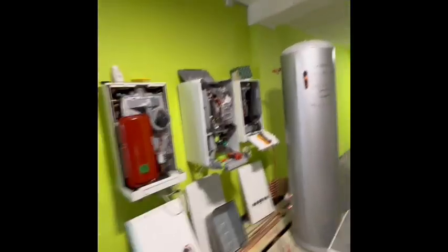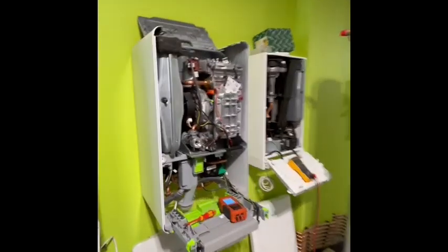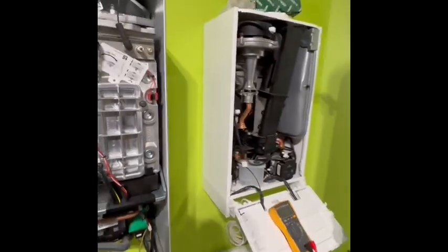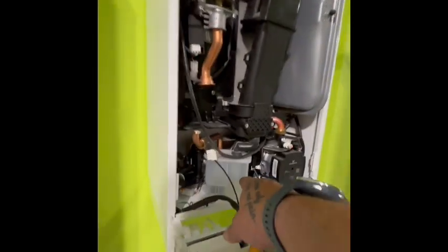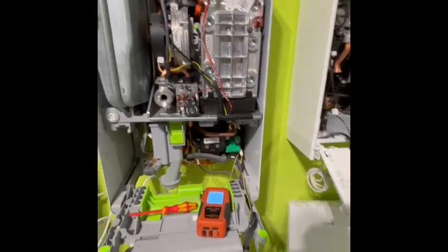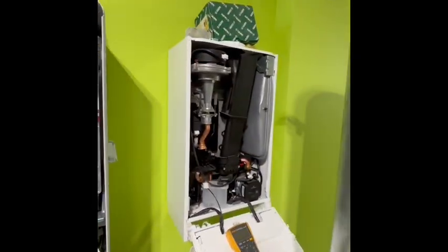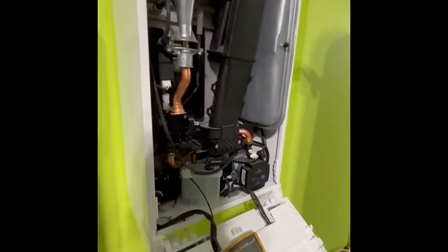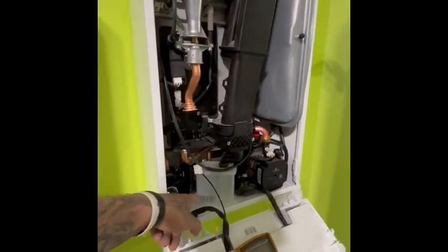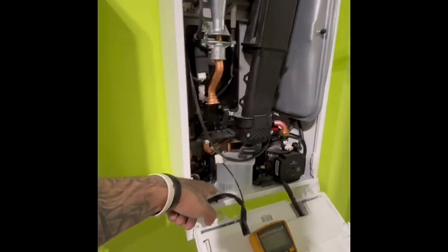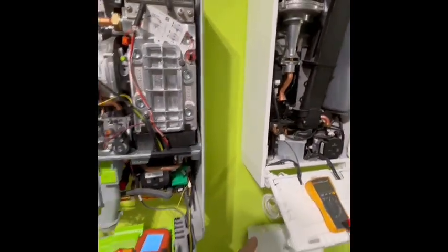Another thing, which is a common thing on boilers to cause an ignition fault, is a blocked condense. So the traps block up down there, or the condensate pipe leading away from the boiler is actually blocked. So generally, how we approach these is take the trap out, we'll clean the trap out, we always blow down the pipe. We've got a little pipe that we connect onto it and we blow down that pipe to make sure that's clear.